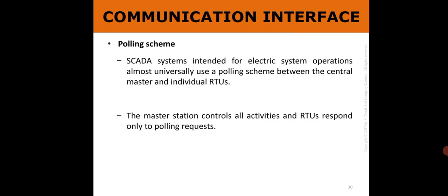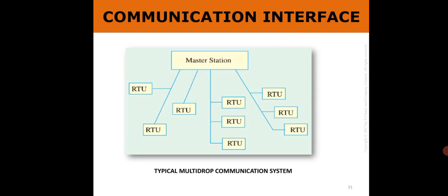Next is the polling scheme. SCADA systems intended for electric system operation almost universally use a polling scheme between the central master and individual RTUs. The master station controls all activities and RTUs respond only to polling requests. This is the typical multi-drop communication system. The master station is then connected to the RTUs.